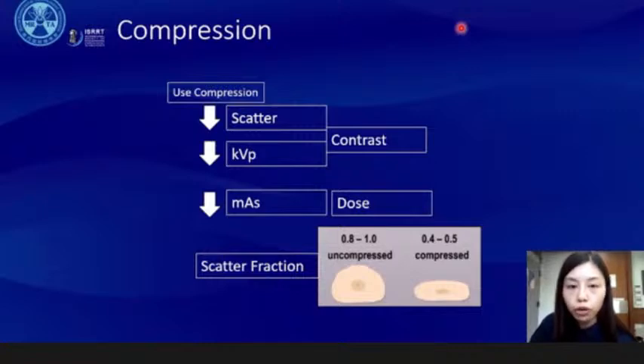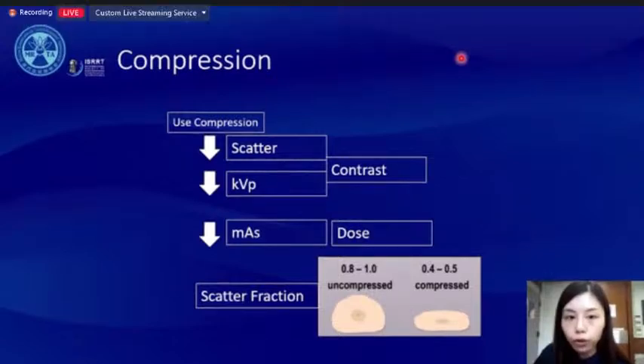Compression is also very necessary to separate overlapping breast tissue, and it will minimize artifacts from patient motion or breathing, which in turn produces a clearer image of the breast. The typical compression force used in mammography is usually between 100 and 200 newtons.